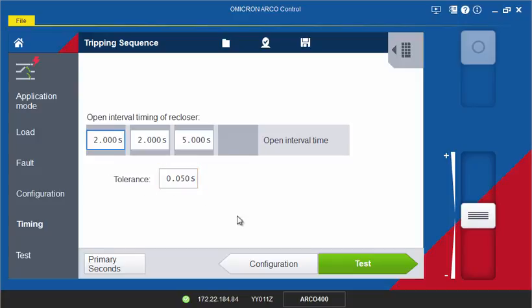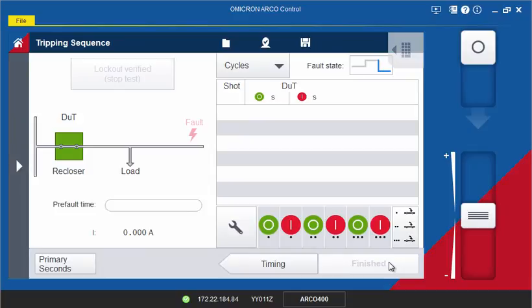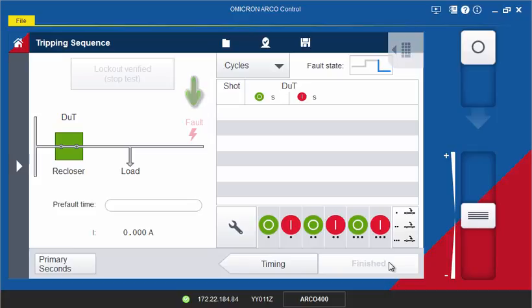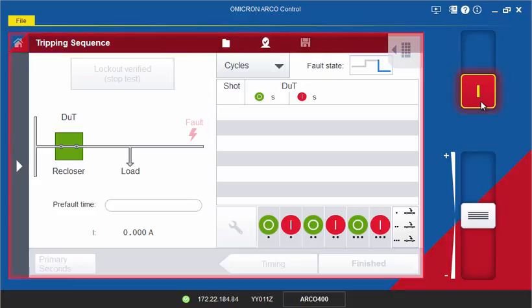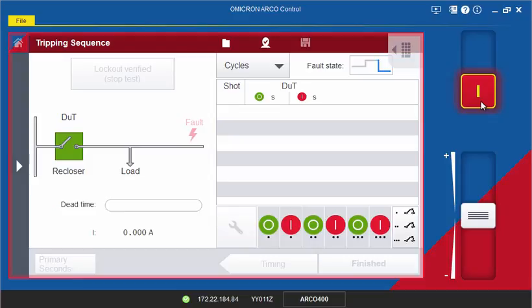Now let's start the test. The current state of the recloser is visualized in the animated picture on the left. After applying the pre-fault for the defined time, the fault is applied, which is indicated by the fault symbol. The software will now go through the fault and open sequence until the device finally locks out in an open position.